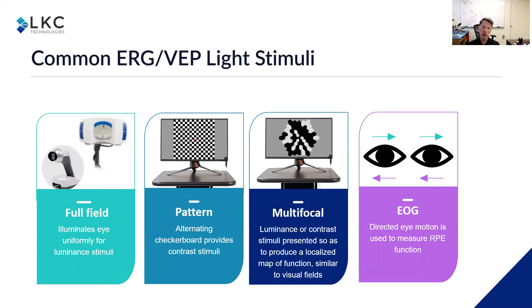Some common ERG and VEP light stimuli include a full field stimulus. Here's a miniature handheld Ganzfeld called RETeval, and here's a bigger Ganzfeld for two eyes called a Sunburst, part of our UTAS system. Those full field stimuli illuminate the eye uniformly for a luminance stimulus. You can also have a pattern-based stimulus, like a checkerboard pattern that alternates which squares are white and which squares are dark, for a contrast stimulus, or you can go from a checkerboard to a uniform gray. You can also have multifocal stimuli that can generate either a luminance or contrast stimulus presented in such a way as to localize the response of the visual system, similar to how visual fields can localize the response.